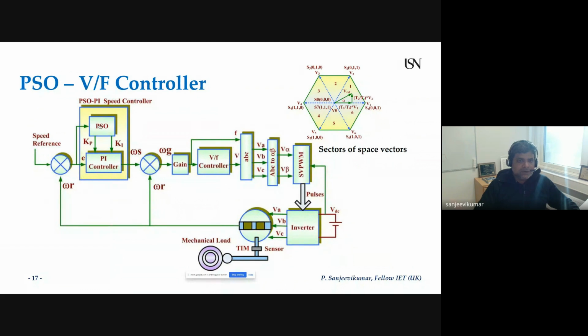The advantage is that during low speed it behaves very dynamically compared to a PI regulator. We generate the synchronous speed, compare it with the actual rotor speed, and generate slip. The slip is given to the V/F controller, where we calculate the frequency and voltage, and convert these signals from 3-phase to 2-phase, where alpha controls the flux and beta controls the torque. This is then given to the modulation system, which controls the inverter for the required speed, torque, etc.